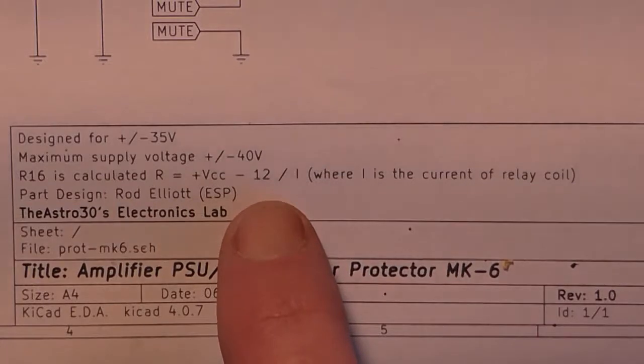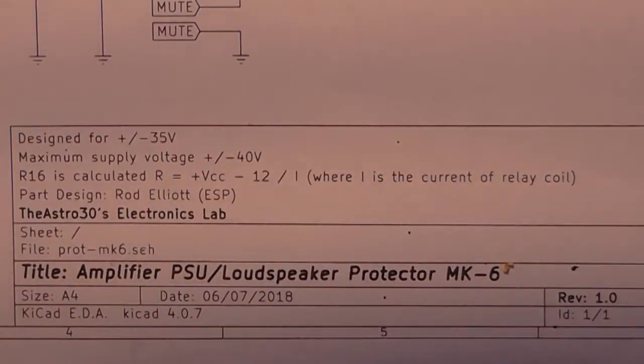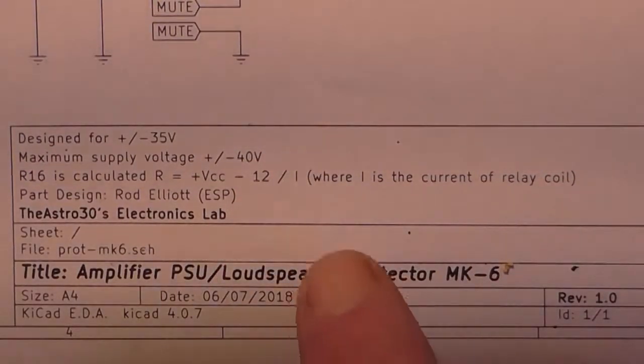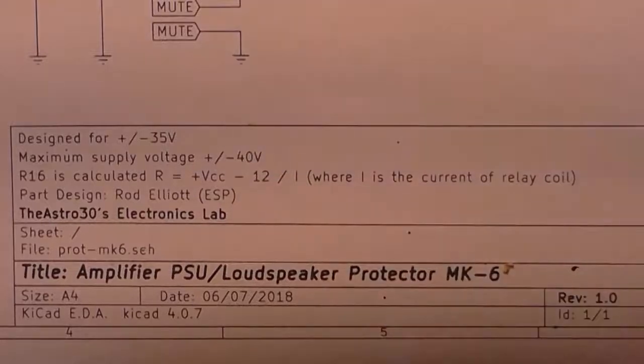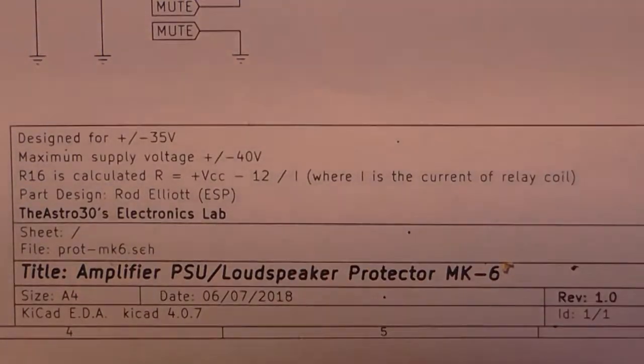You could use a 24 volt relay coil if you like, it makes no difference. You just change that to 24, divided by the current of the relay coil, let's say by I, where I is the current of the relay coil. Then once you've worked out the current of the relay coil, because there's 2 of them, as I said, you're then going to have to use the power law to calculate the wattage of the resistor required.